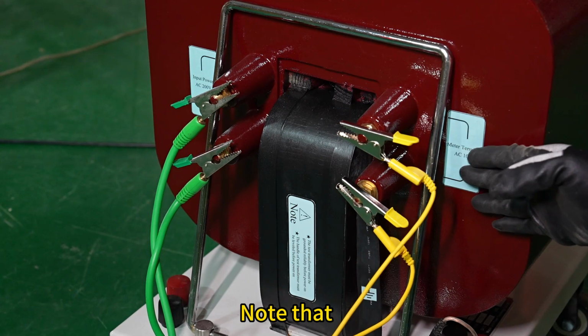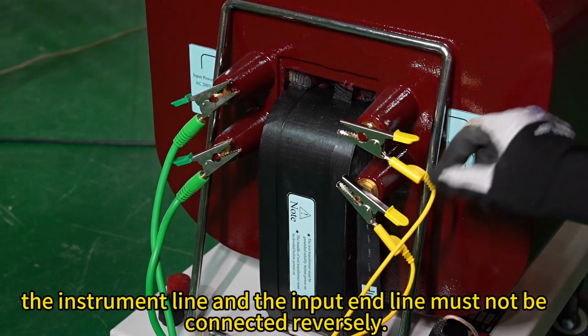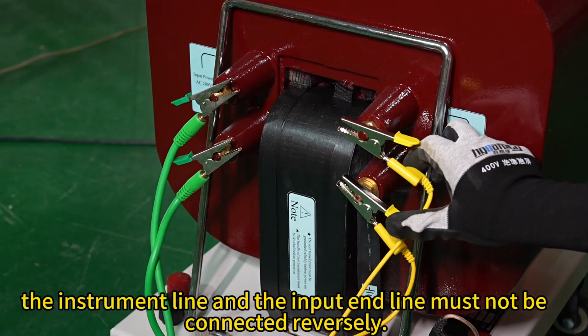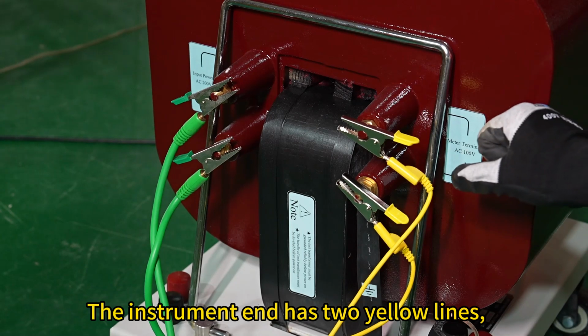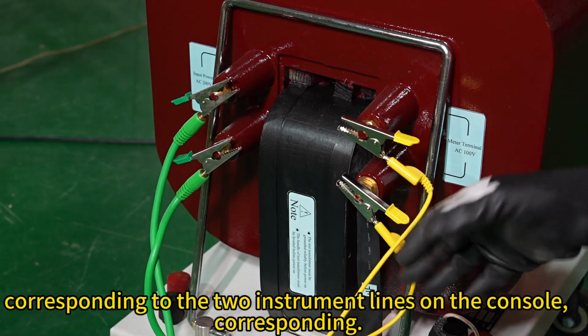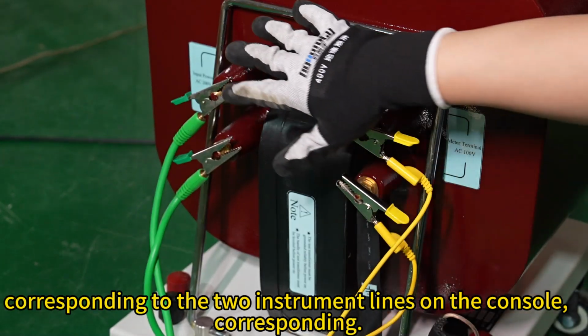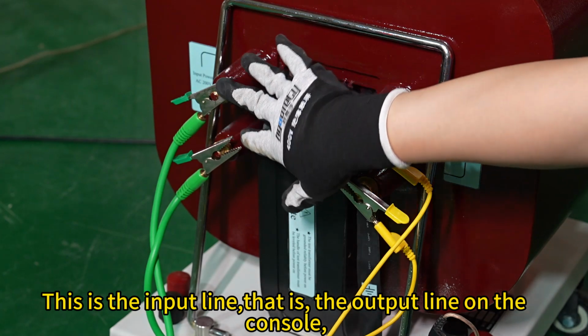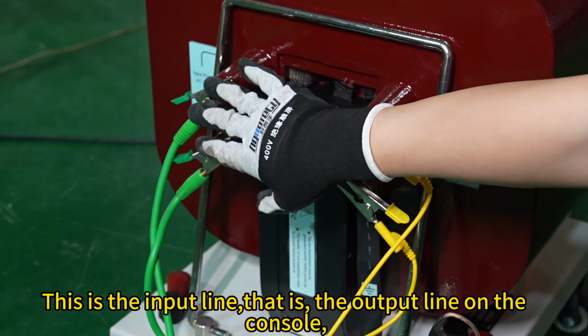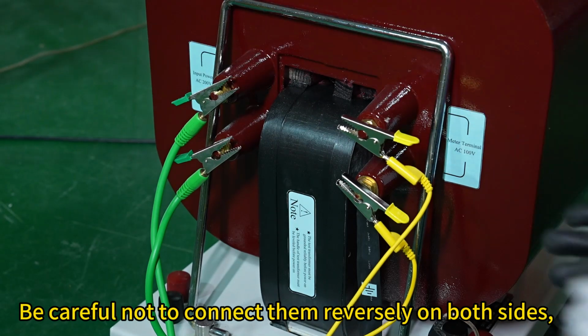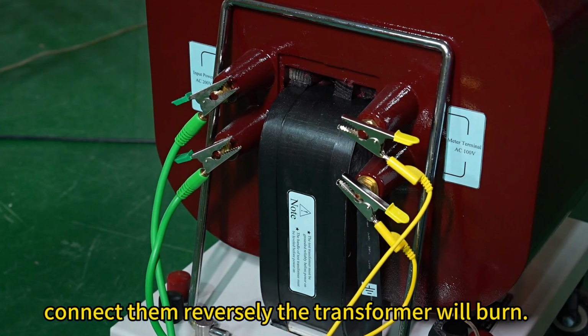Note that the instrument line and the input end line must not be connected reversely. The instrument end has two yellow lines, corresponding to the two instrument lines on the console. This is the input line, that is, the output line on the console, and they correspond. Be careful not to connect them reversely on both sides. If you connect them reversely, the transformer will burn.